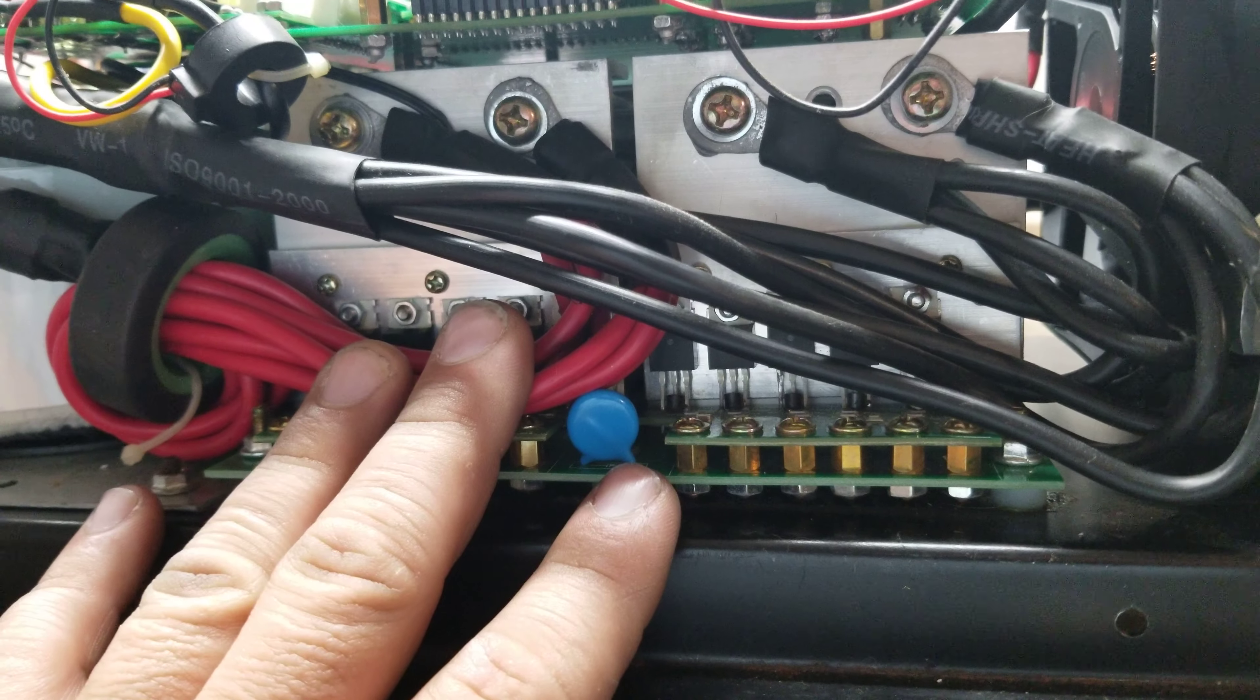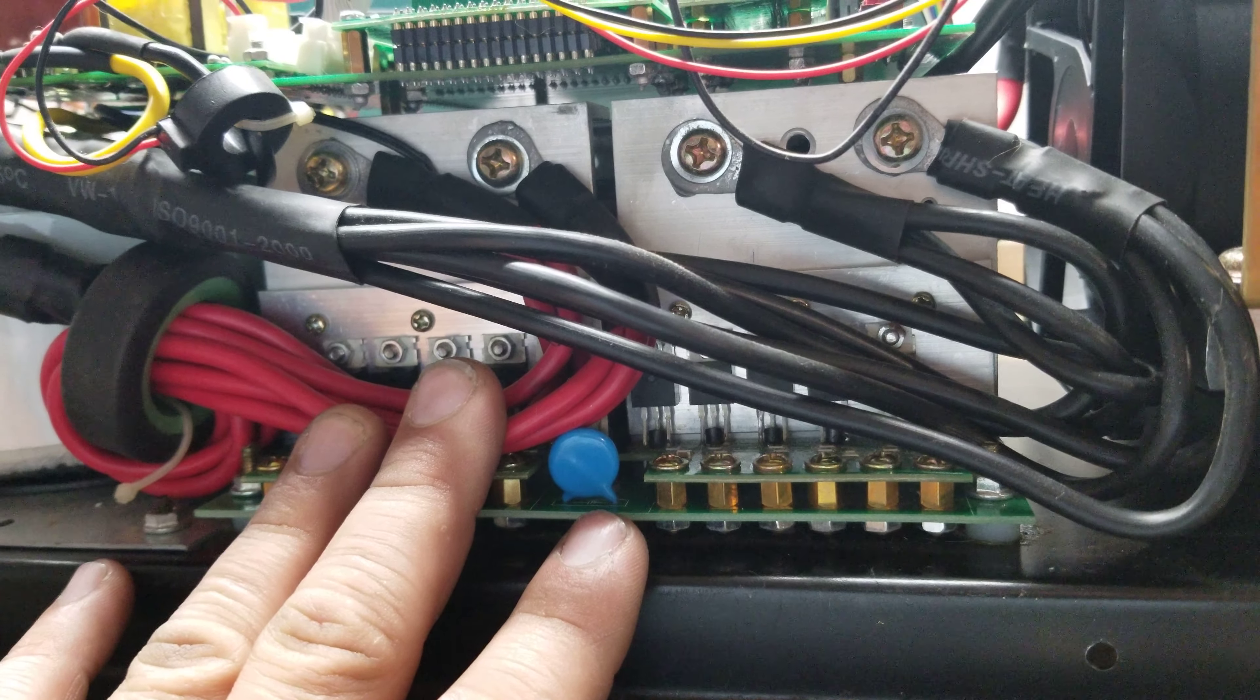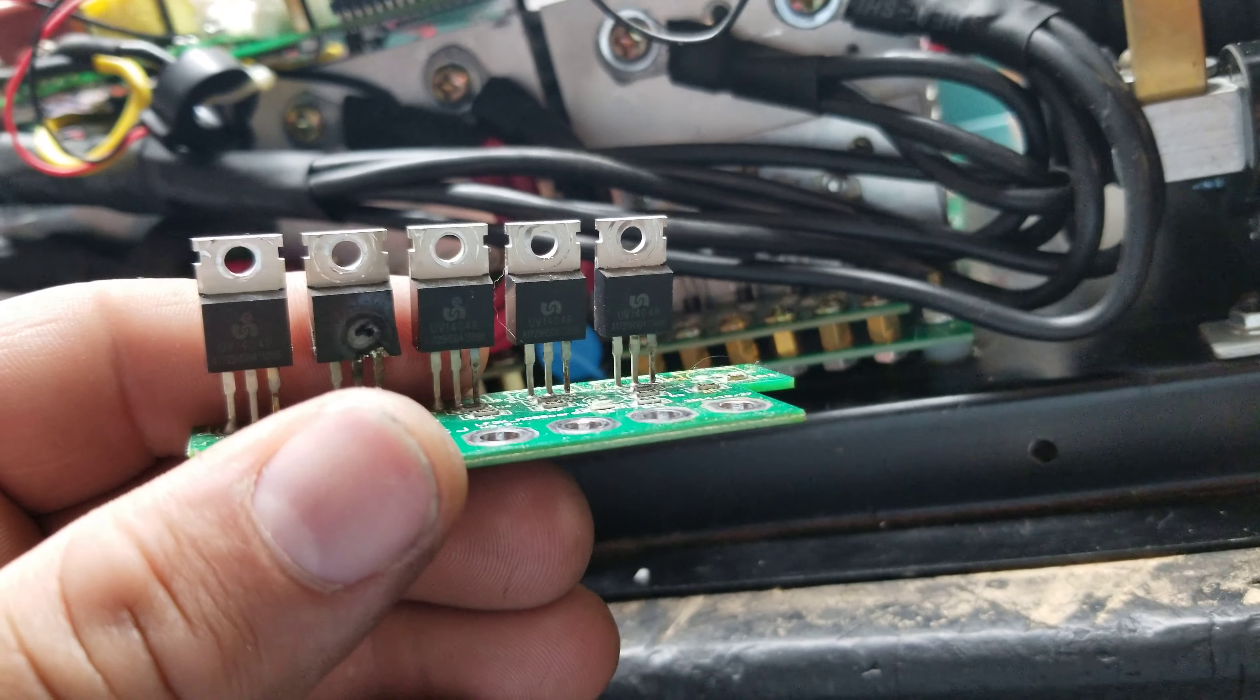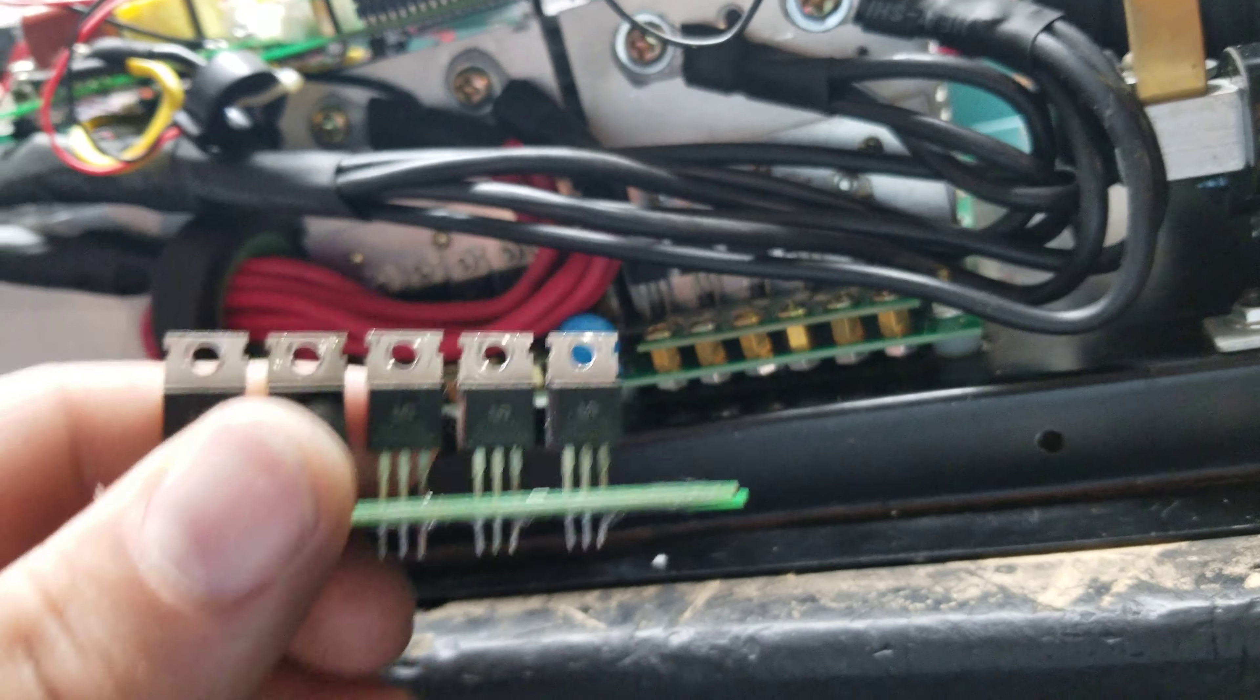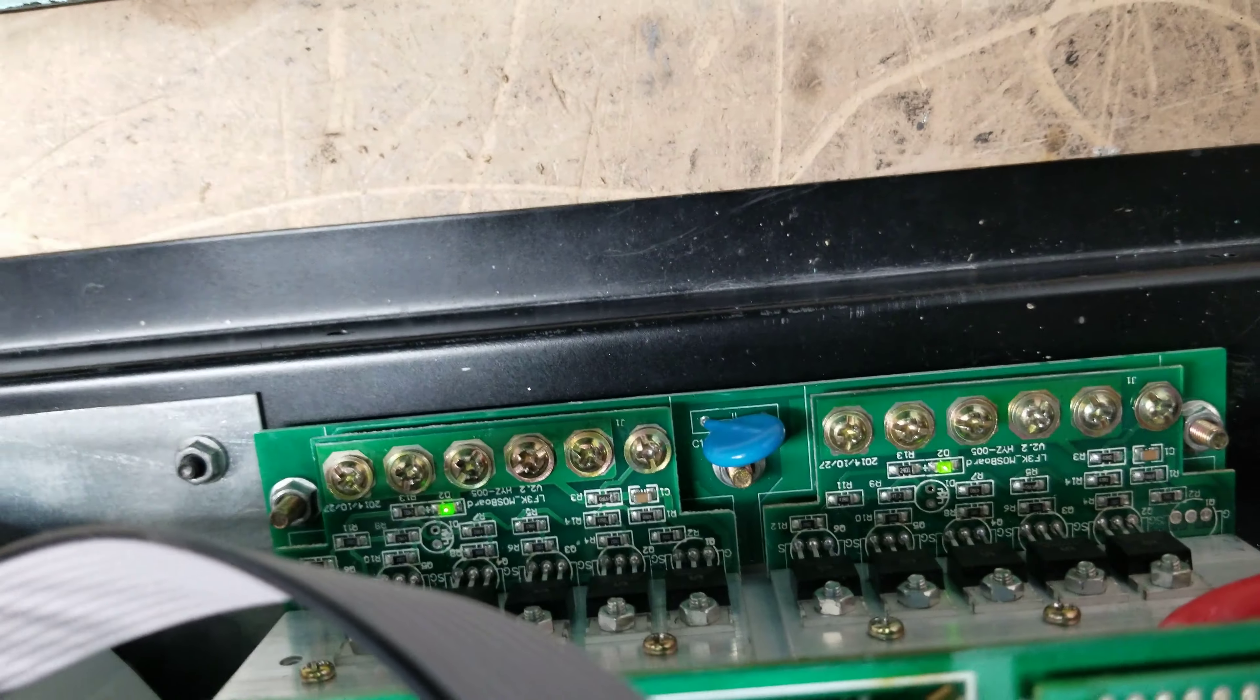So it's always a good idea that if you have a MOSFET board failure, such as like this, that you replace all four. Now, I know some of you might think that's a cash grab or a money grab, but that's not a joke, because this thing here, you can see that it's not lit up. These look like they're still lit up a little bit, they're slowly discharging.